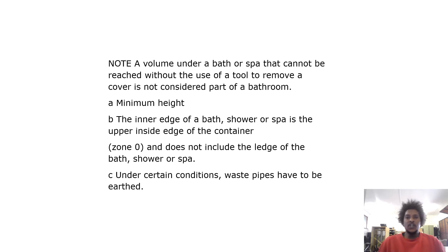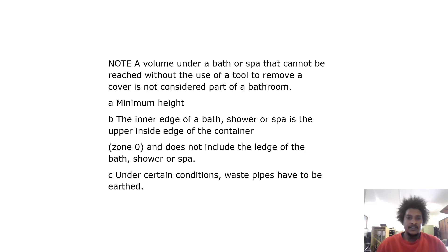A volume under a bath or spa that cannot be reached without the use of a tool to remove a cover is not considered part of a bathroom. The inner edge of a bath, shower or spa is the upper inside edge of the container — zone 0 — and does not include the ledge of the bath, shower or spa. Under certain conditions, waste pipes also have to be earthed.